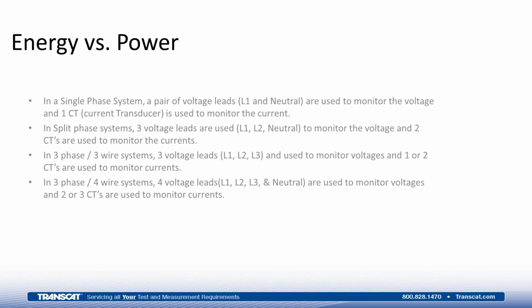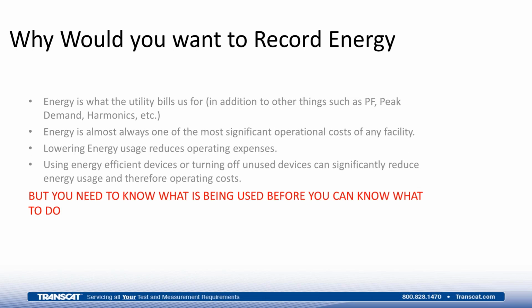The reason I'm explaining this is that this is the complete way to measure power being used by a single-phase, split-phase, or 3-phase load. These would be able to express the instantaneous values of the current and voltage, and display in many cases the wattage being used, by measuring the currents on those loads. This would give us a real-time value, understanding exactly the energy that is being used from a system. We would measure the power and then over time calculate the resulting energy that is being used.